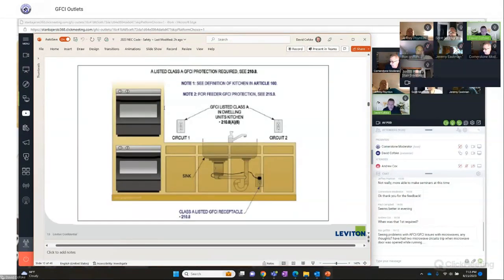This little illustration shows GFCIs typically at the counter. I think the code was that anything within 6 feet needed to be GFCI protected. But as you can see, garbage disposals are now under that 210.8.